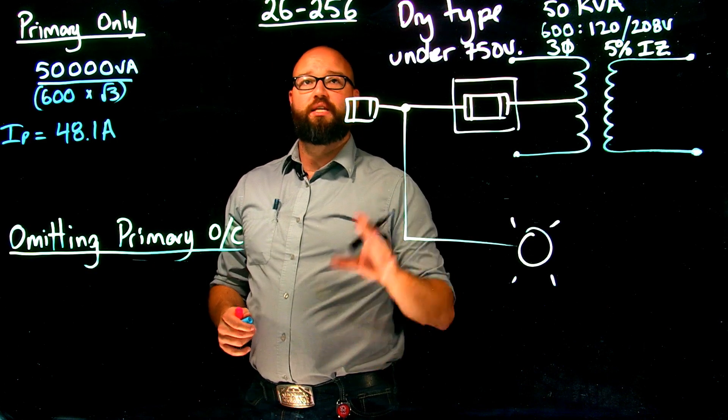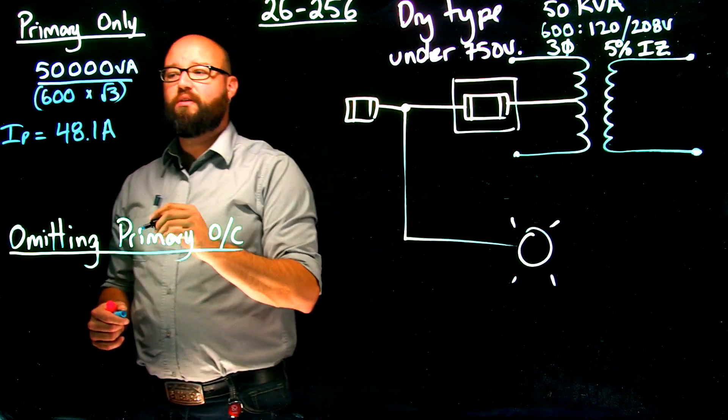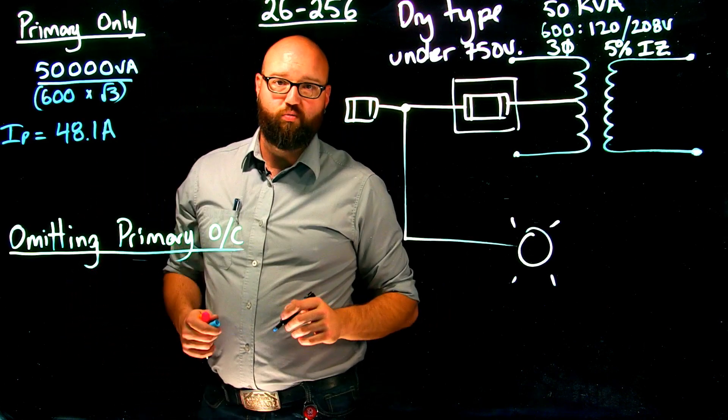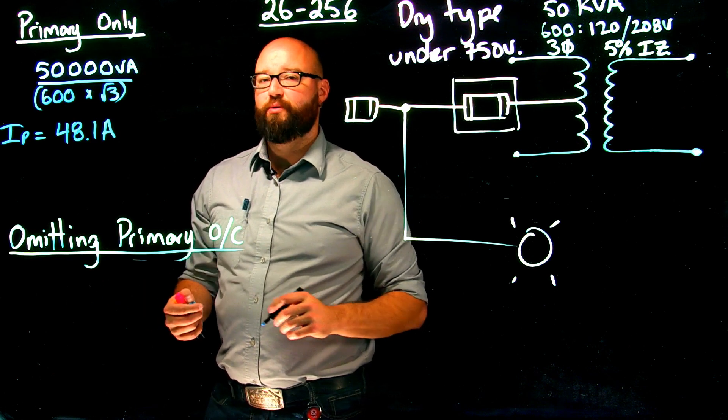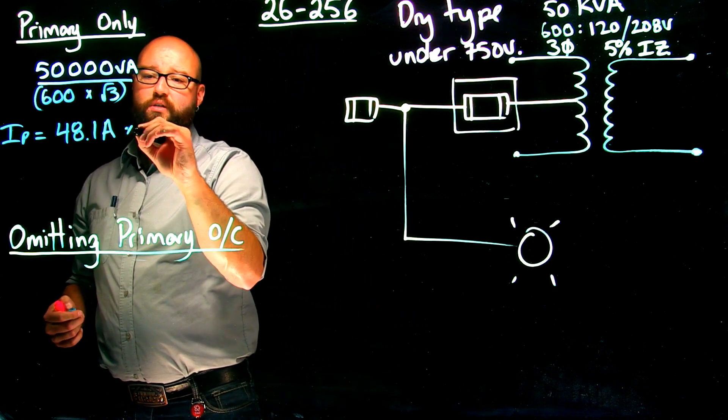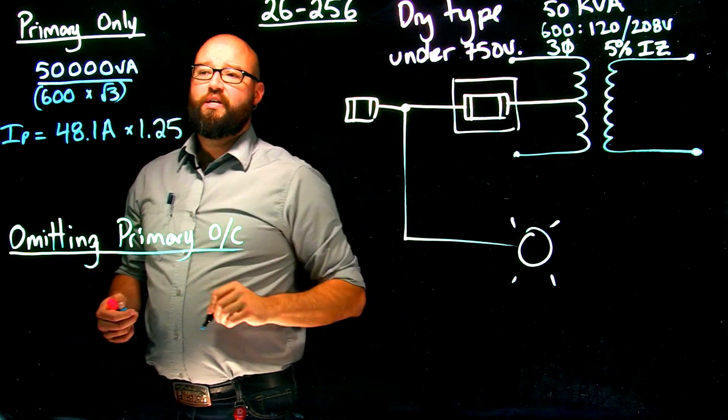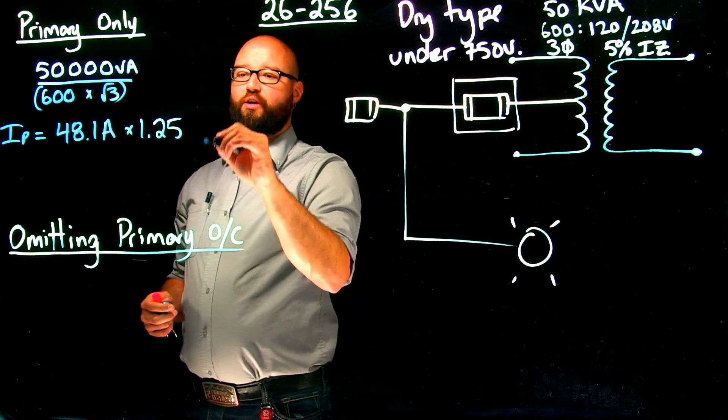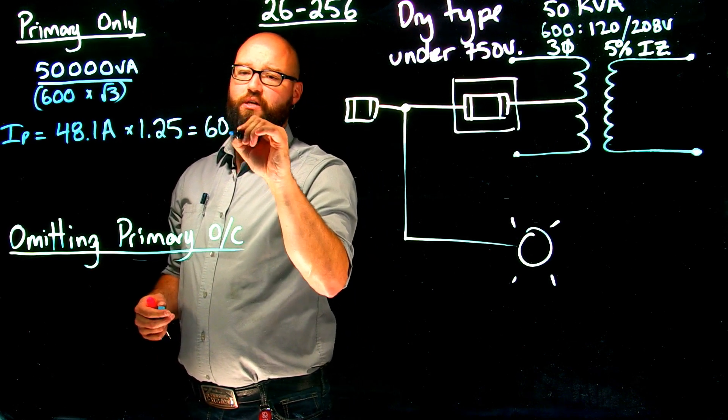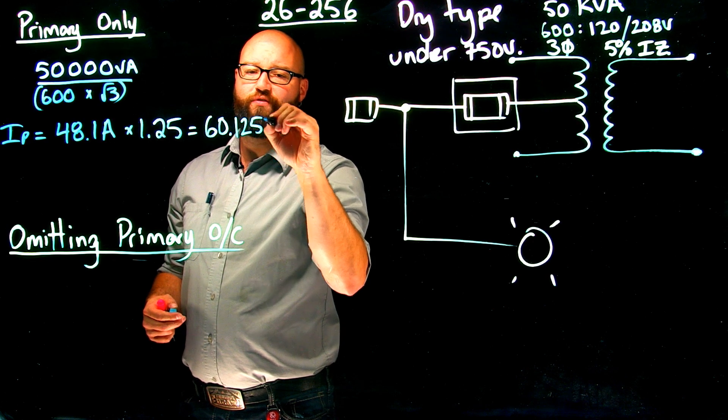And what it tells me, as I said, in 26-256 subrule one is we're going to use 1.25 or 125% as our multiplier. So times 1.25 gives me a max value of 60.125 amps.